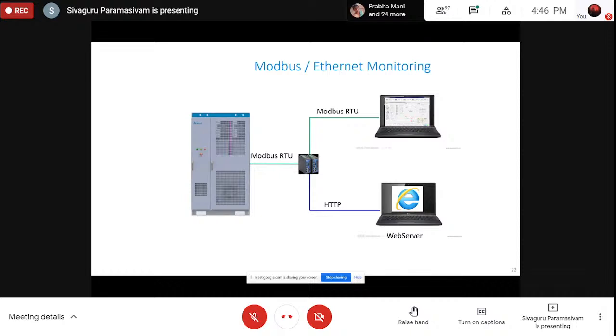What you see here in this drawing is one of the protocols called Modbus RTU, Remote Terminal Unit. There are multiple protocols: Profibus, DeviceNet, CANopen, CAN bus, Genius bus, Ethernet. All are communication protocols, but we pick the communication based on certain requirements, like the distance between two equipments. Is it 1 meter or 1 kilometer? And then the baud rate, the rate of data transfer or bits transferred per second. And then the number of devices connected in the whole network. Is there just 3 nodes, as we call them, or is there like 1,000 nodes? There are also 1,000, 2,000 nodes in certain networks. So when the number of nodes changes, the communication protocol should still help the network communicate properly without getting delayed, without shutting down, without transferring wrong data.